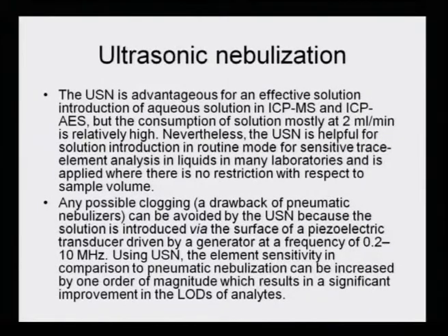Any possible clogging, a drawback of pneumatic nebulizers, can be avoided in ultrasonic nebulization, because the solution is introduced via the surface of a piezoelectric transducer driven by a generator at a frequency of 0.2 to 10 megahertz.